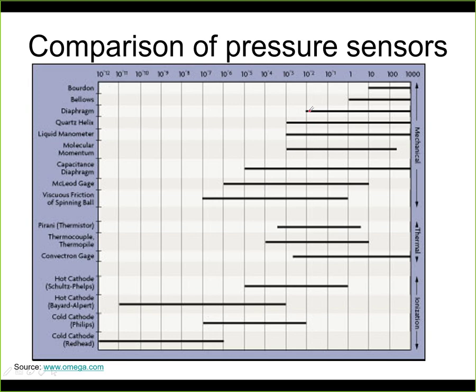And the diaphragm type can typically measure to lower pressures. So here you can see approximately the estimate 10 to the power of minus 2. This is like a typical range. So here in this range we may expect the diaphragm to work. We have discussed also some other types, like for example the liquid manometer. We've discussed that last week, so this is approximately the same range like the diaphragm.